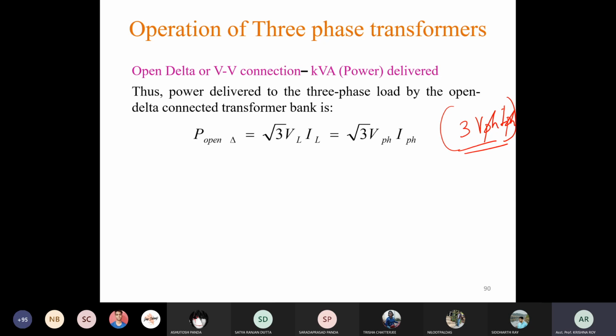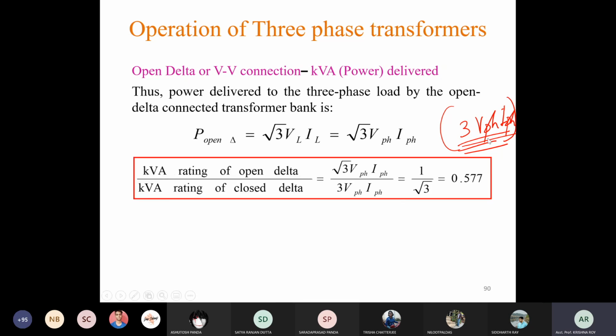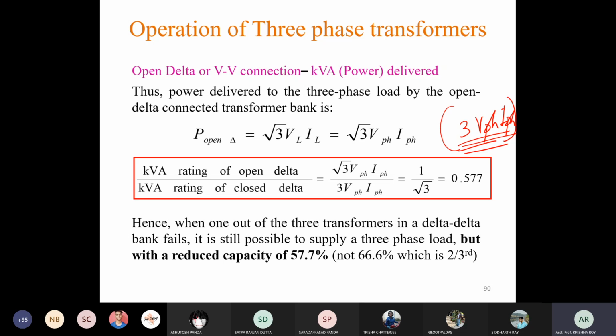So the kVA capacity has reduced to root 3 V phase I phase from 3 V phase I phase. We can see the load carrying capability has reduced. Therefore, the factor by which this capacity has reduced is 0.577. That means we can conclude that when one out of the three transformers in a delta-delta bank fails, it is still possible to supply a three phase load, but with a reduced capacity of 57.7%, not 66.6%.